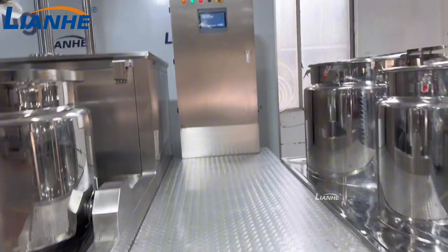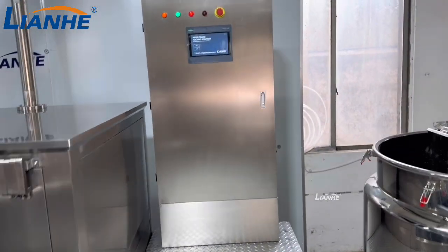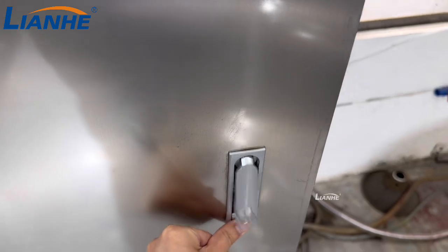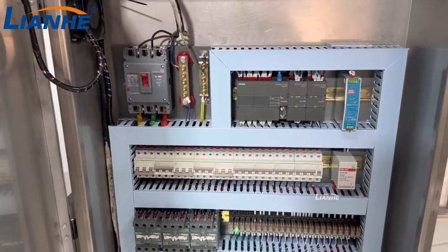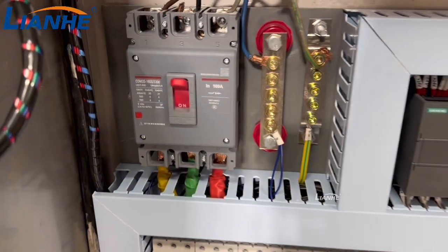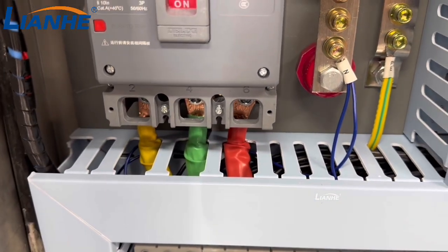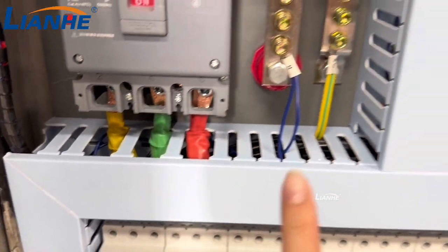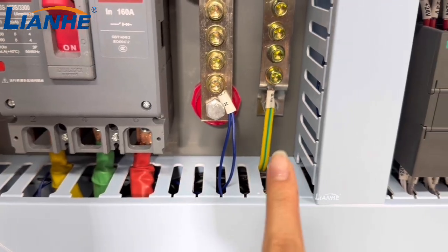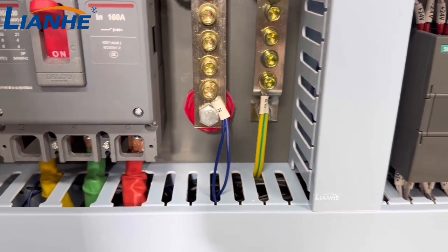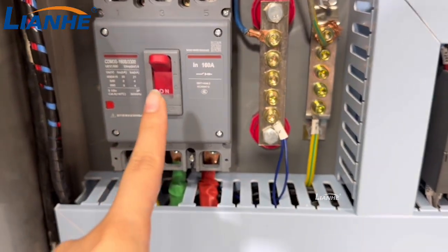And then after the assembly, you should connect to your factory power. Open this electric box here, and then you may check inside. Here we have L1, L2, L3 wire, these 3 wires, and then this is the neutral wire and ground wire. You should connect these wires and then open here.